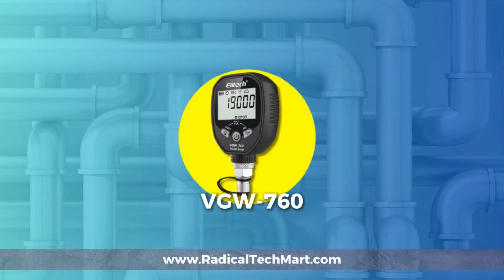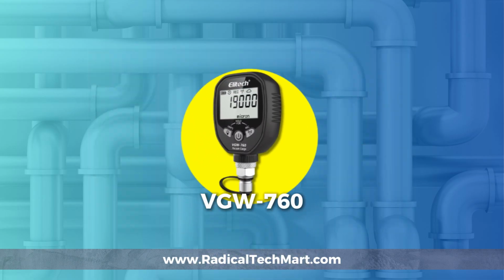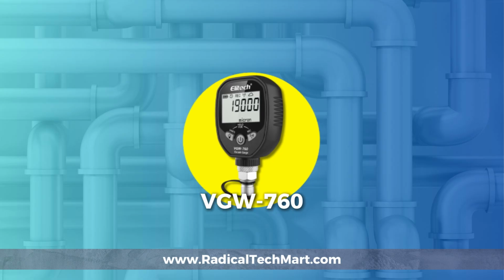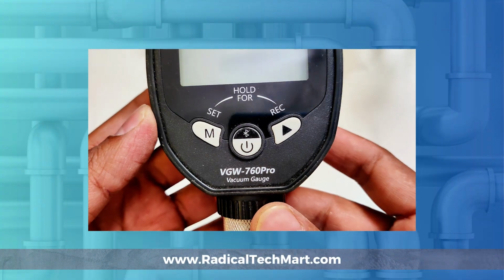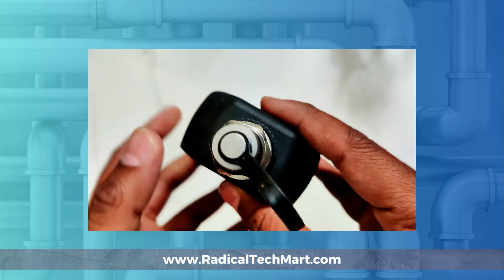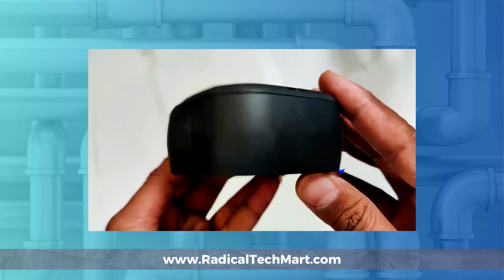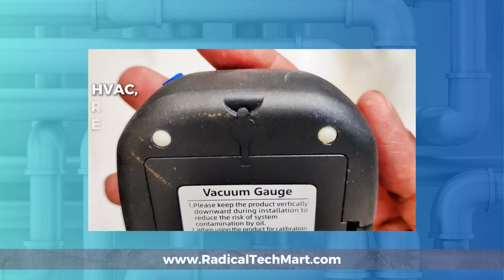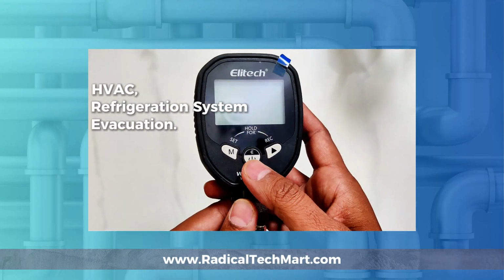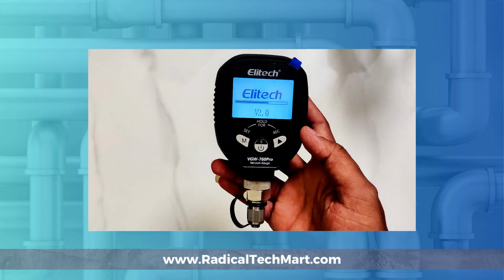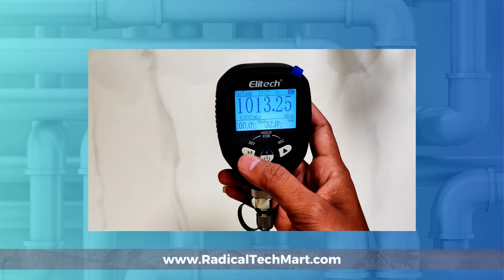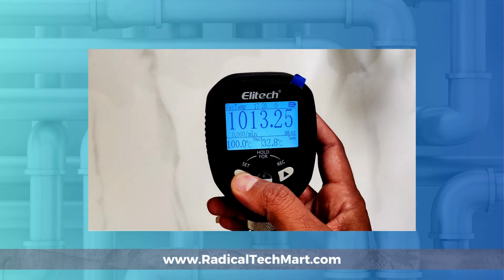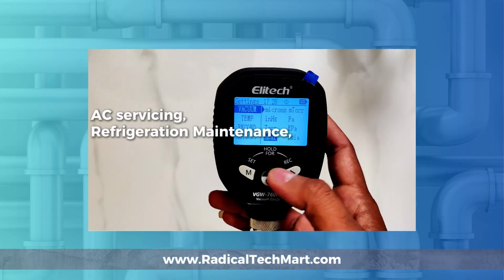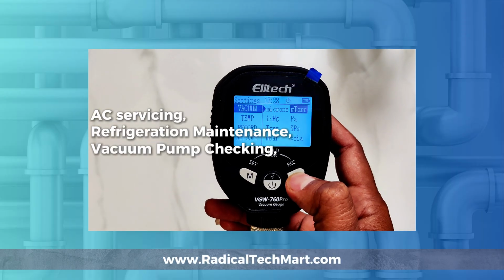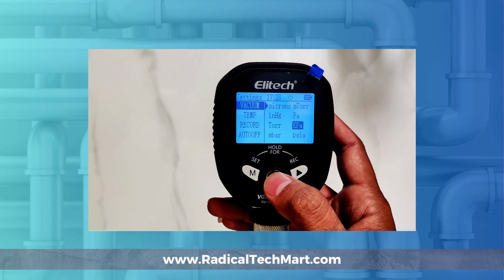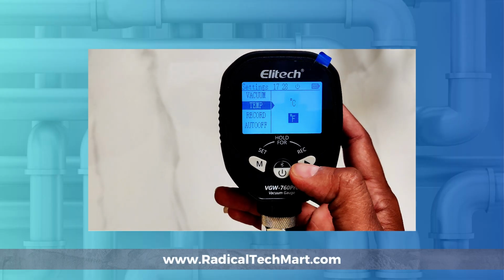In this video, we will understand the Elitech VGW-760 wireless digital vacuum gauge. The Elitech VGW-760 is a wireless digital vacuum gauge. It is mainly used for HVAC and refrigeration system evacuation. In simple words, it helps you check the actual vacuum level inside the system. This is useful during AC servicing, refrigeration maintenance, vacuum pump checking, and leak checking. It helps the technician work with more confidence instead of guessing.